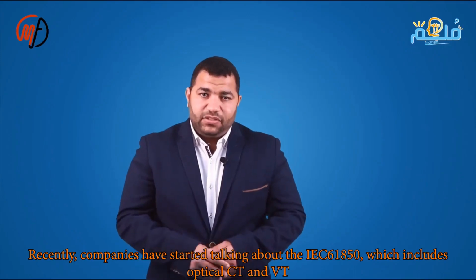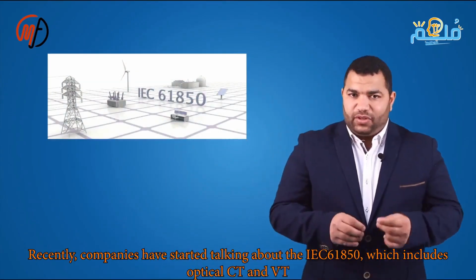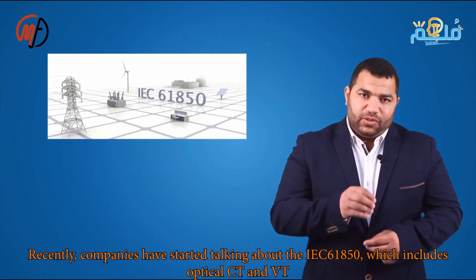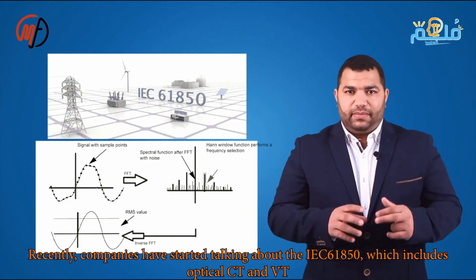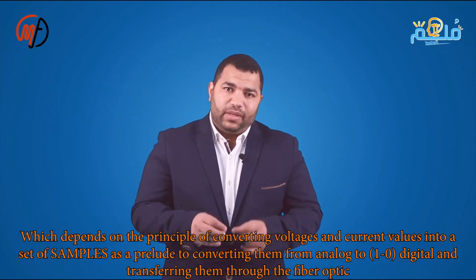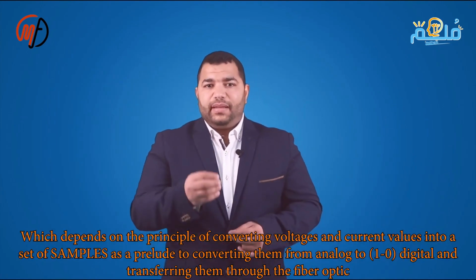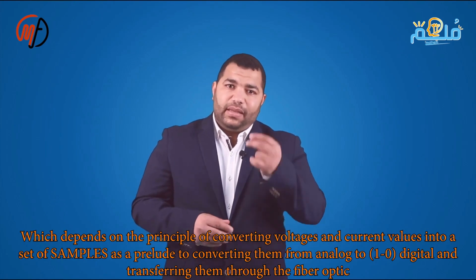I discussed IEC 61850. This technology converts voltage and current into digital samples via fiber optics. These transformers lack a core, avoiding saturation and electromagnetic reliance, and are smaller than traditional CTs and VTs.